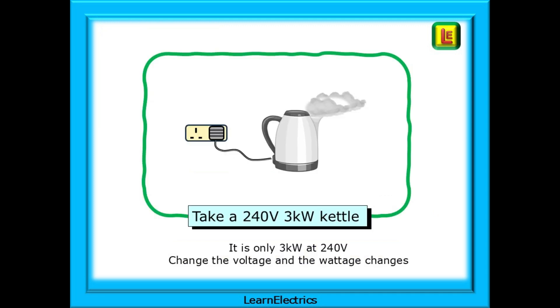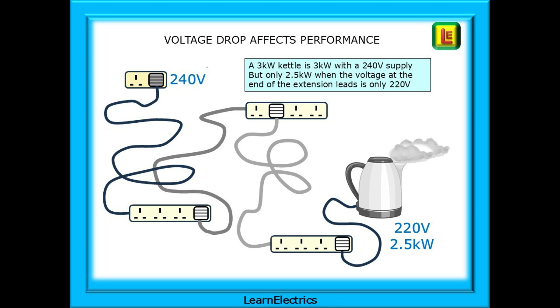Let's take a simple 240 volt electric kettle rated at 3 kilowatts. It's only 3 kilowatts at 240 volts. If we change the voltage, then the wattage changes. So how does this affect the performance of the kettle? Here we have our 3 kilowatt kettle, which we said is only 3 kilowatts with a 240 volt supply. Imagine that there is no available socket at the coffee making table, so somebody has run a series of extension leads to it. Problem solved. The kettle works, and that's all that matters. But the kettle might now be rated at 2.5 kilowatts, because the voltage at the end of the extension leads is only 220 volts. Reduce the voltage, reduce the wattage at the point of use, and the kettle takes longer to boil the water.